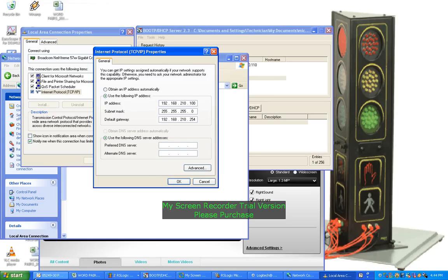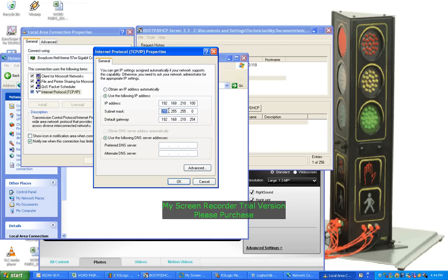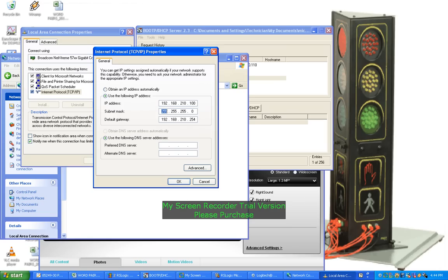Now, the IP address of the computer should be different to the IP address of the device that you are trying to communicate with. Usually the first three digits in the IP address will be the same as the device you're addressing, and the last one will be a little bit different. So I've got 192.168.210.100 there. I think I've got these figures from the manual for the PLC. Subnet Mask 255.255.255.0, which is very standard, and Default Gateway 192.168.210.254.